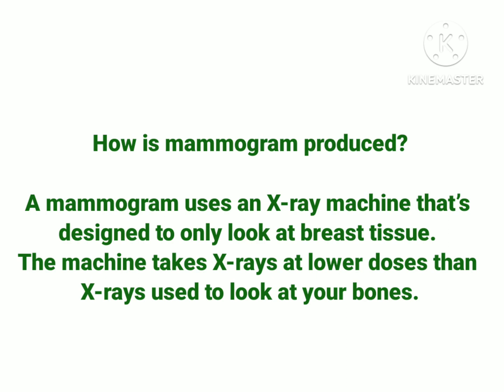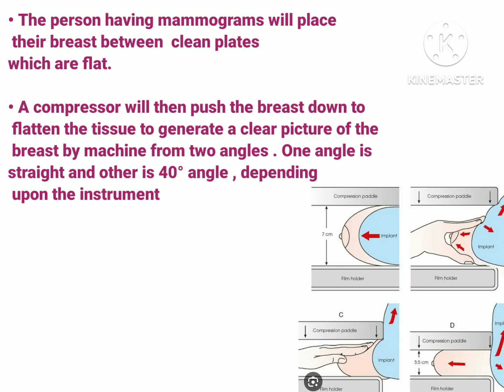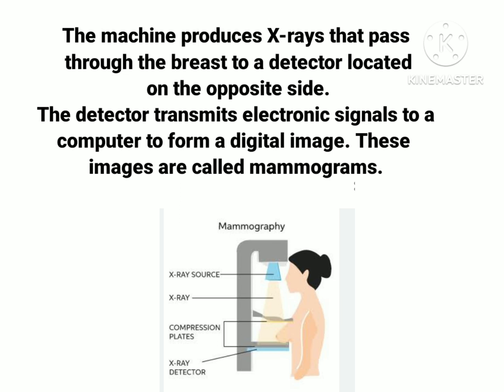Now let's discuss how a mammogram is produced. This mammogram uses an x-ray machine designed to look only at breast tissue, using low x-ray doses — unlike a general x-ray machine that uses high radiation doses to visualize bones and other soft tissues. In the first step, the person having a mammogram places their breast between clean flat plates. A compressor above pushes the breast down to flatten the tissue so that a clear picture is generated. The machine takes pictures in two angles: one straight, and another at a 40-degree angle, captured when the machine is rotated 40 degrees.